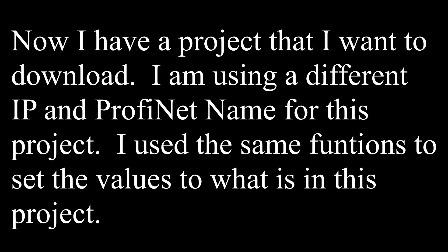Scan the network again, make sure that it actually picked up the settings that I wanted. Because wherever you pick, that's the way the PLC will refer to it, and both items, name and IP, have to match.